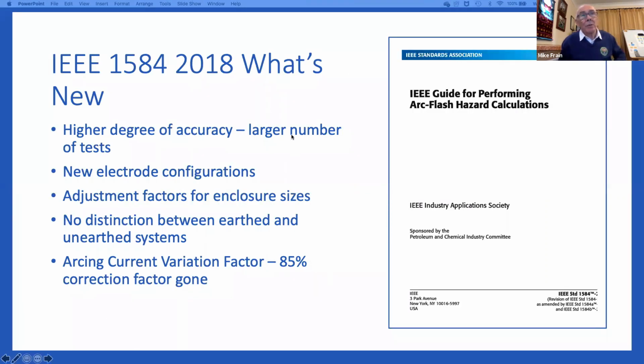Now I'm going to just talk to what's new on standards, and within IEEE 1584, for people that are fully aware of this, I apologise, but there is a higher degree of accuracy. The last print was 2002, which is a long time ago, so this has been coming a long time. The higher degree of accuracy is because of a larger number of tests, and it takes into account new electrode configurations. There used to be 2 electrode configurations back in the 2002 one, either in a box or in air, but now there's 5. I'll talk about those in a second.